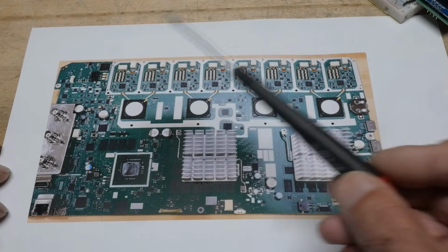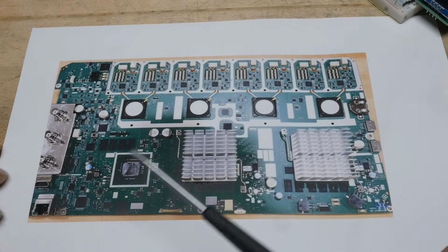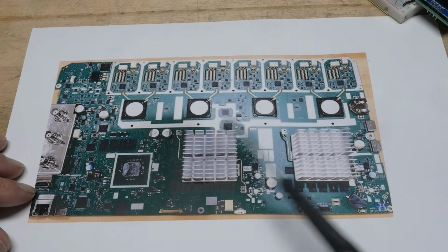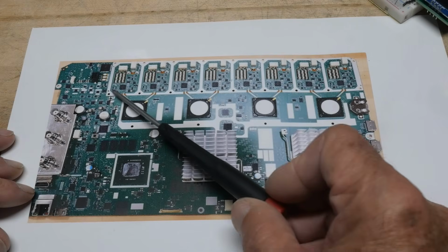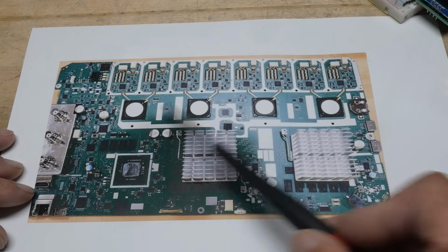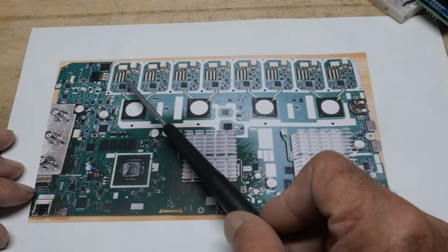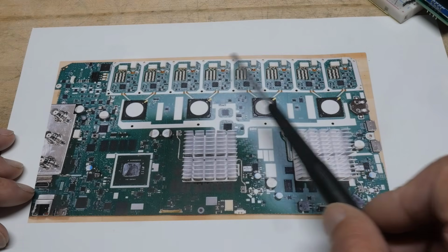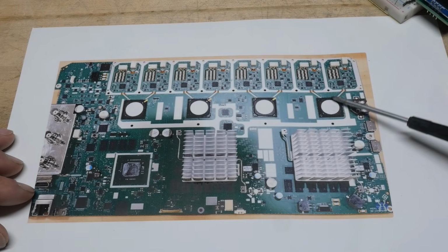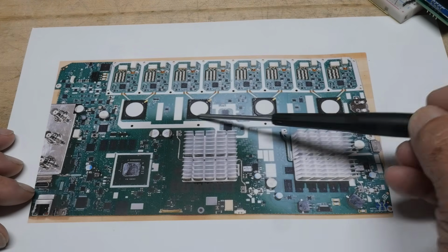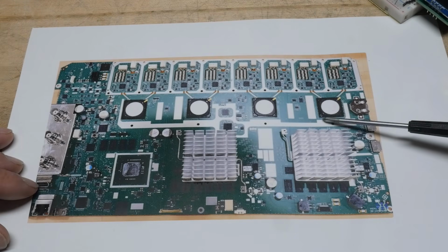Then they run into an ADC, the thing that does the sampling. The 5 gigasamples per second is done with these chips here. And you can see that this chip has 2 inputs, so it's sharing. That was the reason that if I choose channels 1, 3, 5, and 7, then I'm only using half of each of these A to D converters. If I chose all the evens, it would have done the same thing.